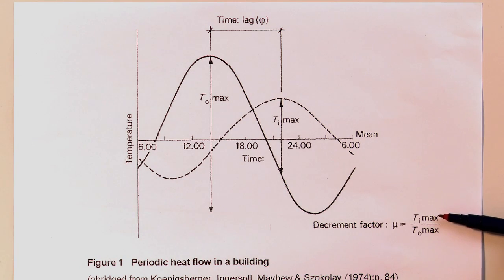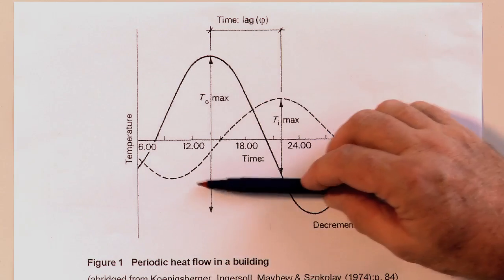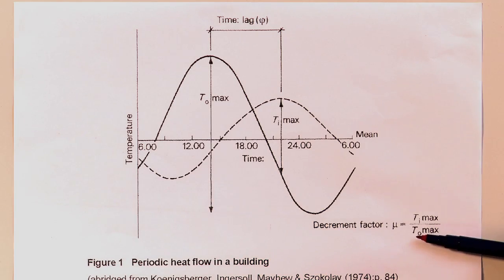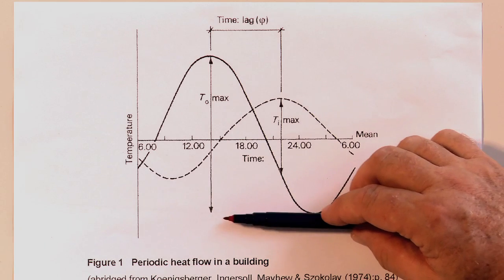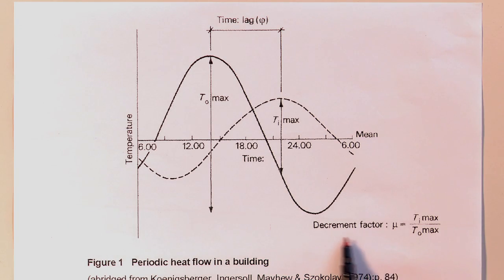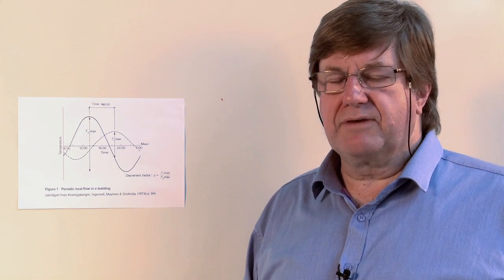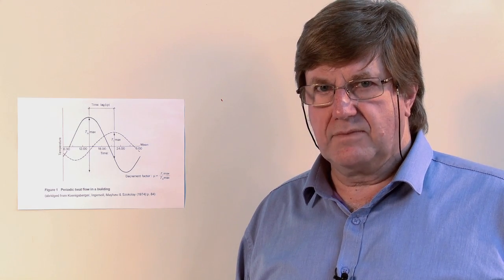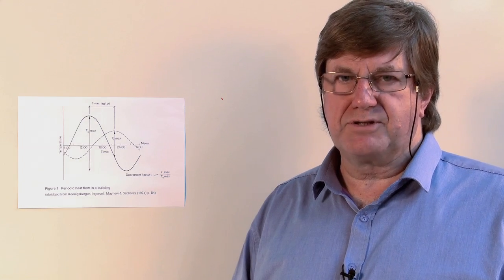The decrement factor is a representation of the temperature difference between the maximum and minimum outside and the maximum and minimum inside. So we have Ti, which is the internal temperature between the peak and the trough, and the outside, which is the peak and the trough. So the decrement factor is Ti over To. Usually in brick veneer construction we introduce some insulation, which also increases the temperature drop.